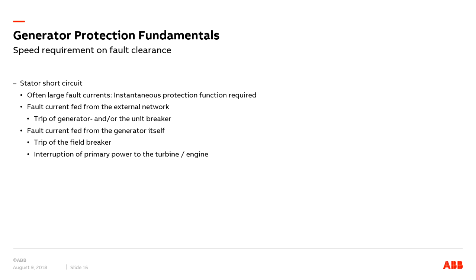So the speed requirement on fault clearance is pretty critical for a short circuit fault, because the short circuit causes a very large current, and so it should be cleared as fast as possible. In a short circuit condition, the fault current is fed from the external network where the generator is connected to, and from the generator itself, because the generator is producing power itself. The short circuit current from the external network, which is often the largest part of the total short circuit current, is interrupted by tripping the generator and/or the unit breaker.